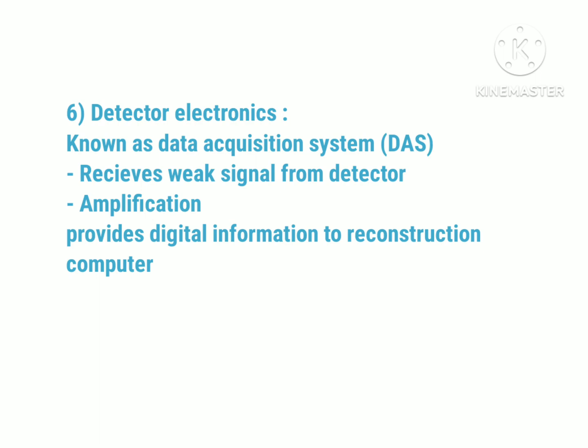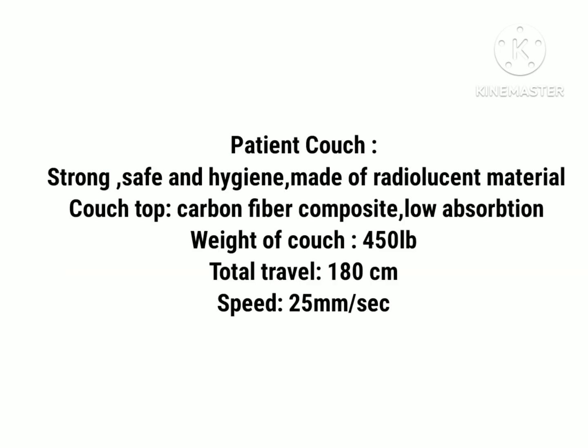The sixth component of the gantry is the detector electronics, known as the Data Acquisition System (DAS). It receives the weak signals from the detector, amplifies those signals, and provides digital information to the computer so that the computer can reconstruct those signals.